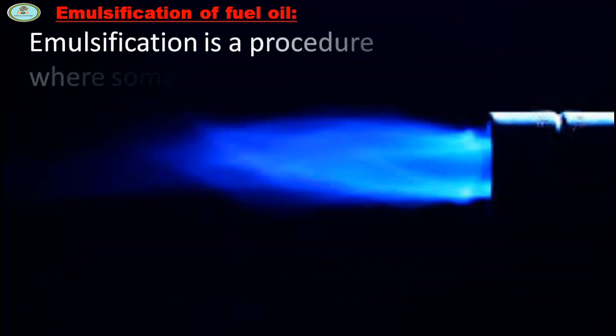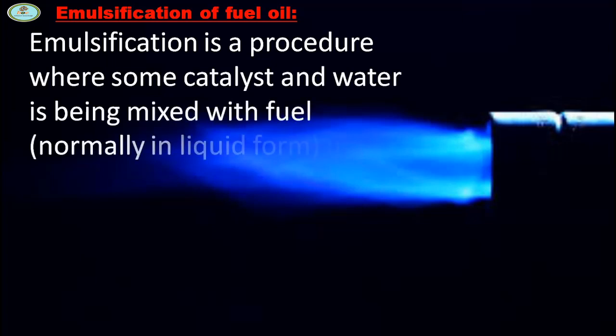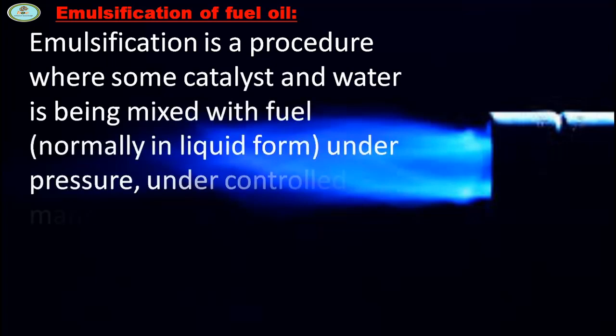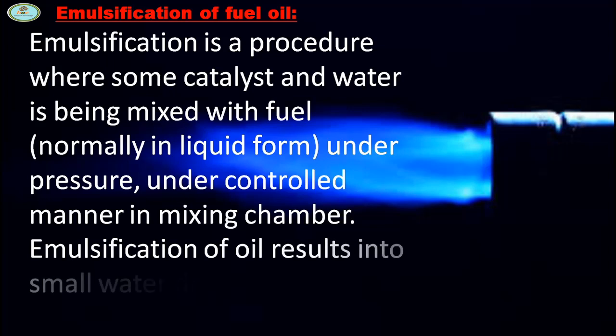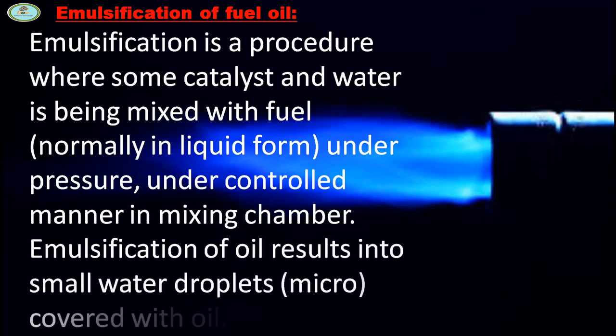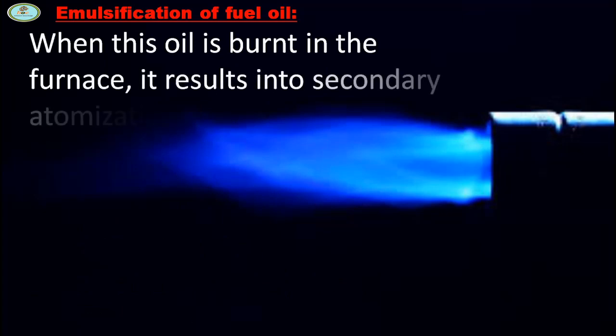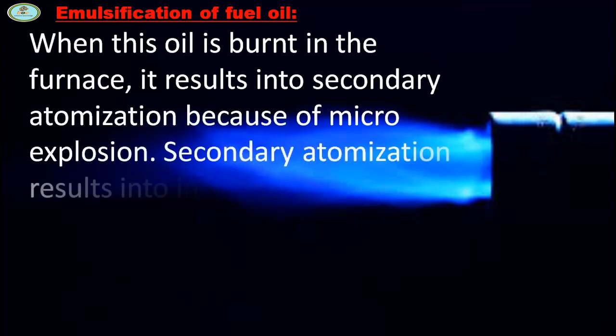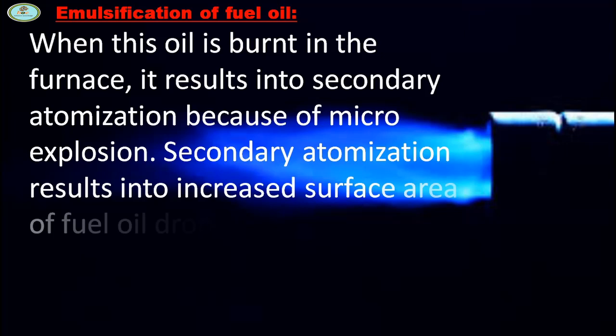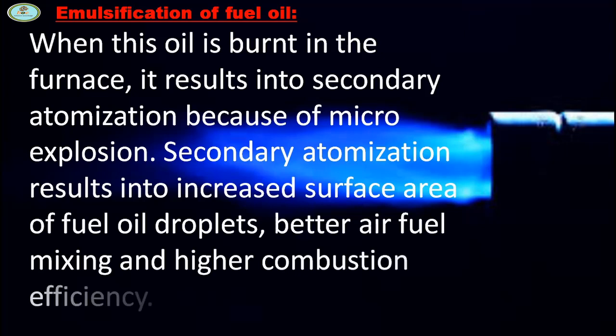Emulsification is a procedure where some catalyst and water is mixed with fuel, normally in liquid form, under pressure in a controlled manner in a mixing chamber. Emulsification of oil results in small water droplets covered with oil. When this oil is burnt in the furnace, it results in secondary atomization because of micro explosions. Secondary atomization results in increased surface area of fuel oil water droplets, better air-fuel mixing, and higher combustion efficiency.